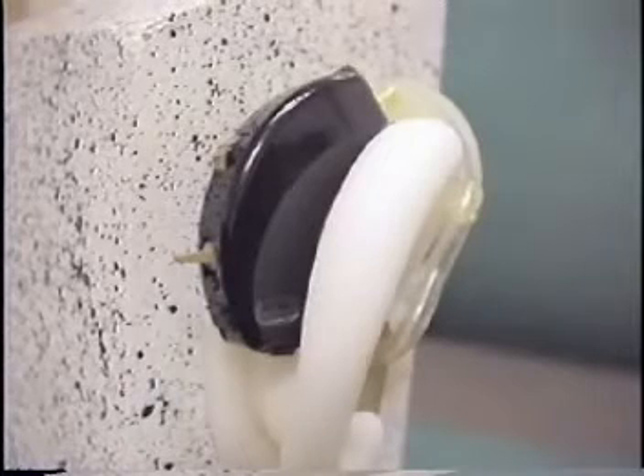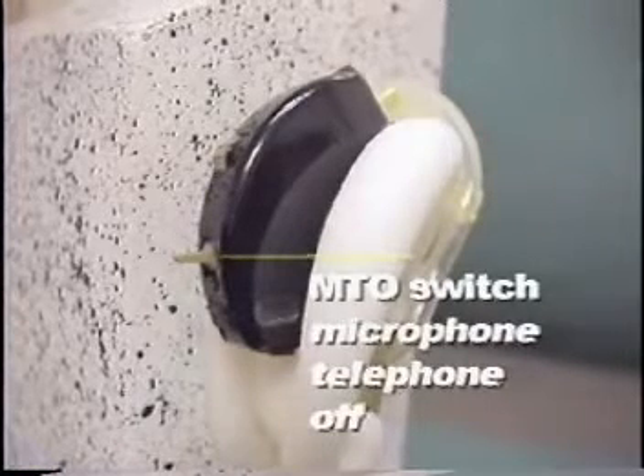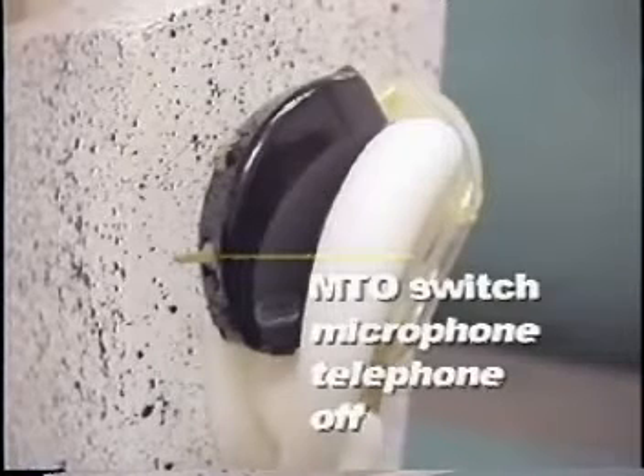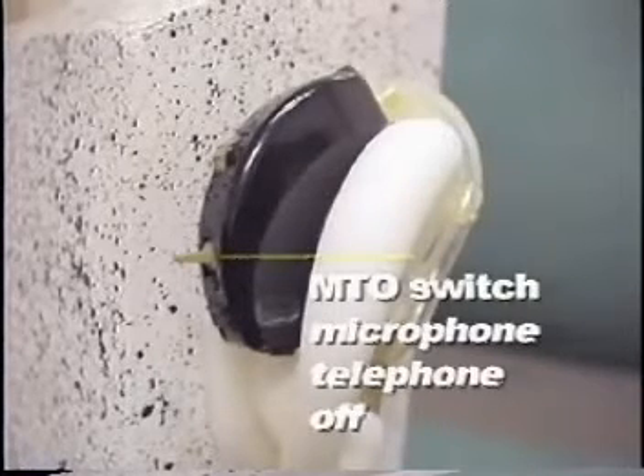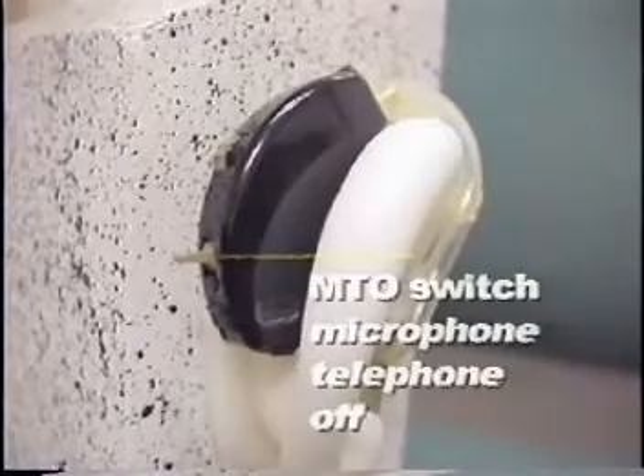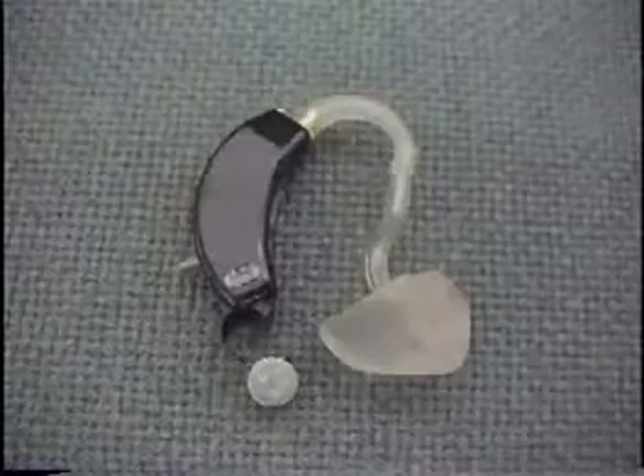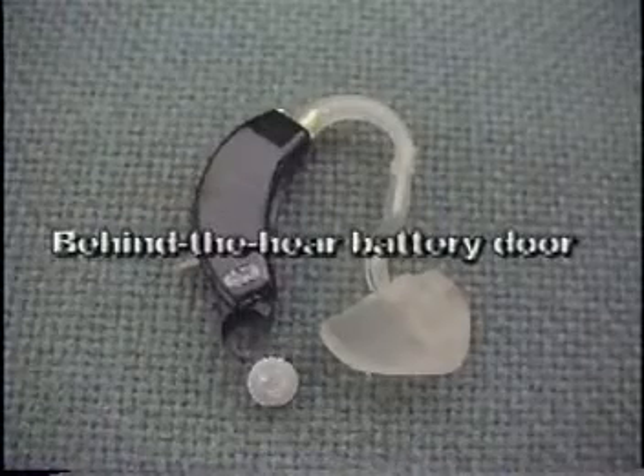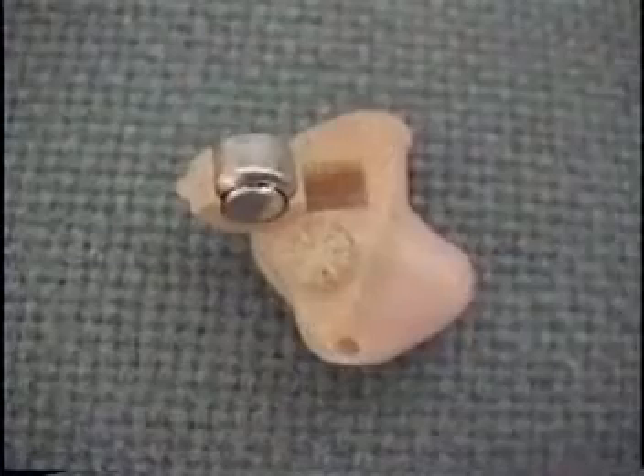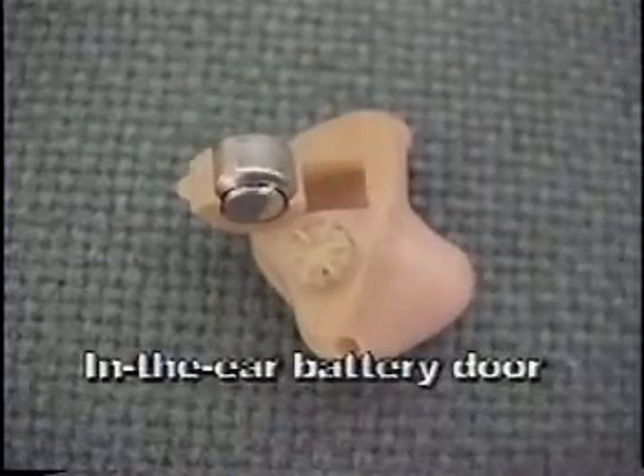Another component that's contained on hearing aids is what's called an MTO switch. The MTO switch stands for microphone, telephone, and off. What you see here are the battery doors for the behind-the-ear hearing aid, and next the in-the-ear style hearing aid. It's important that hearing aid batteries are changed every 1 to 2 weeks depending on the style of hearing aid an individual has. It's often helpful to work over a towel when changing the battery on a table, so if the battery drops, it doesn't roll.